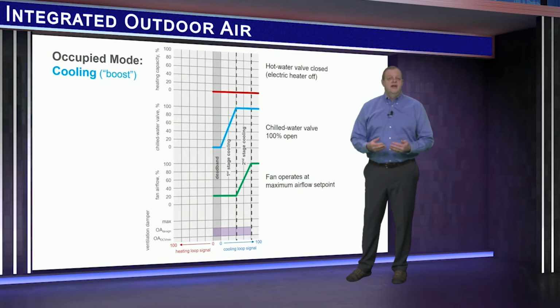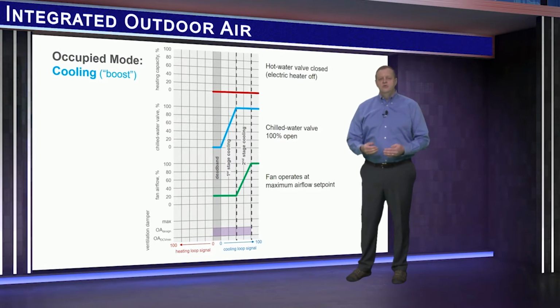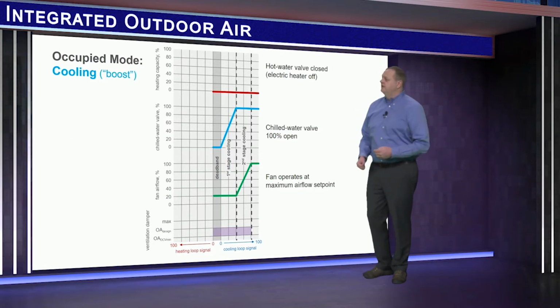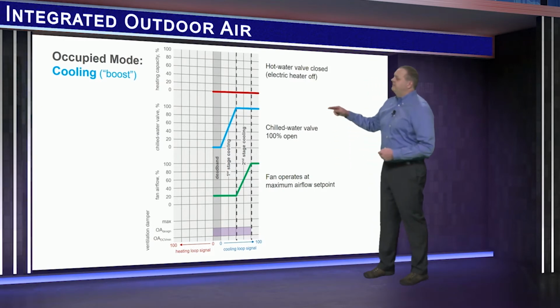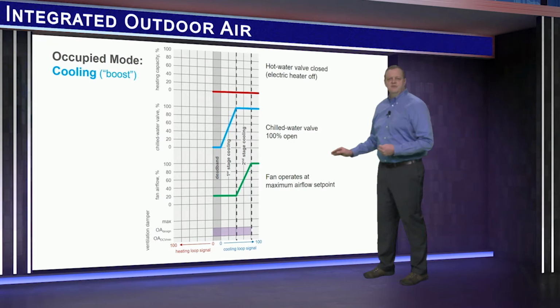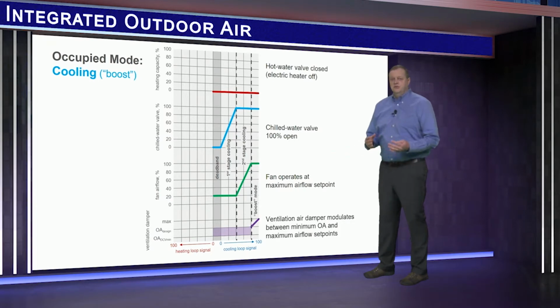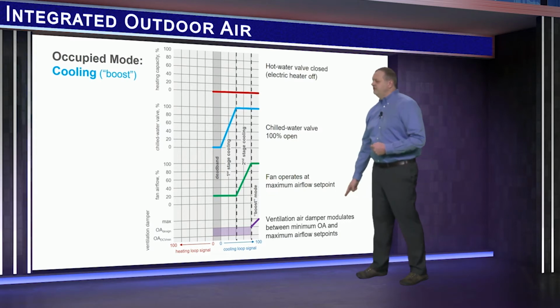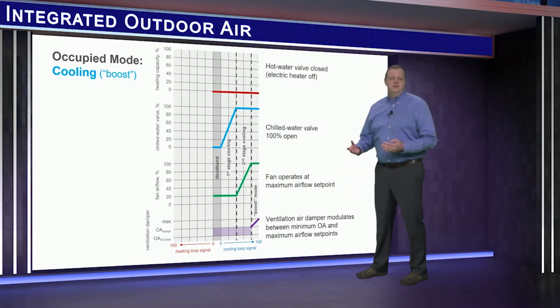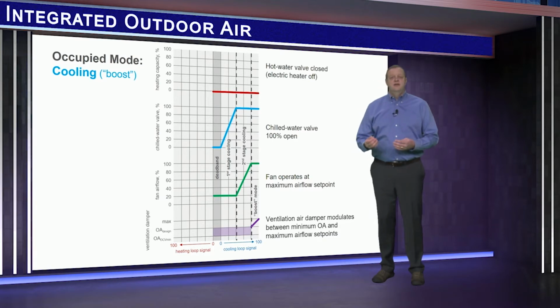But the Trane controller has an added feature which we're calling a cooling boost mode. With the chilled water valve fully open, if this fan reaches its maximum airflow set point and the zone still requires more cooling, the controller can modulate the ventilation air damper further open. This will increase the flow of cool, dehumidified air from the dedicated outdoor air unit.